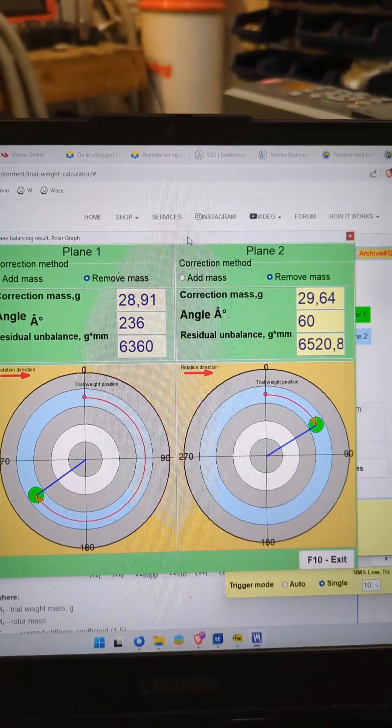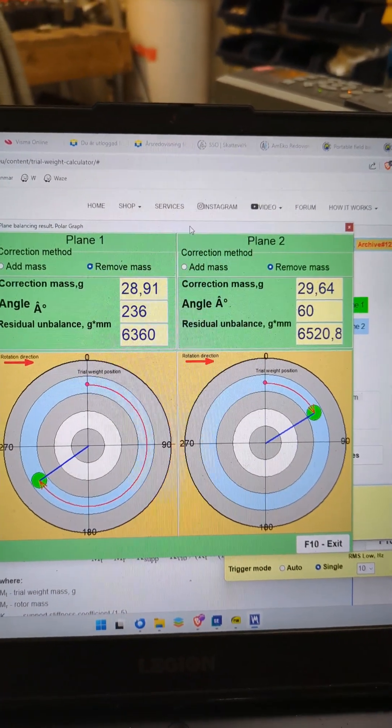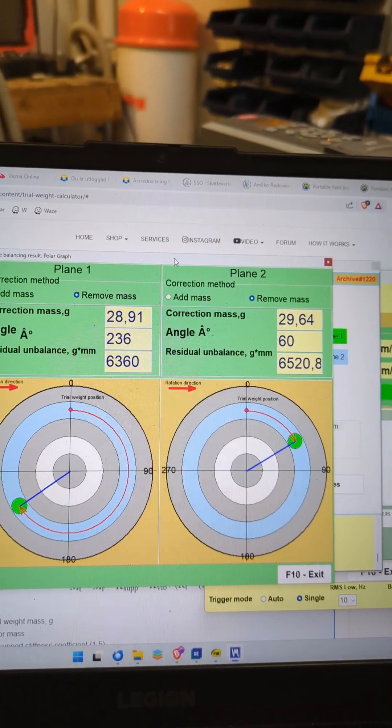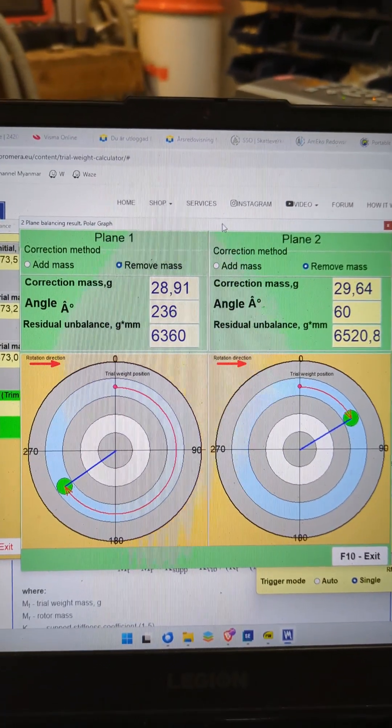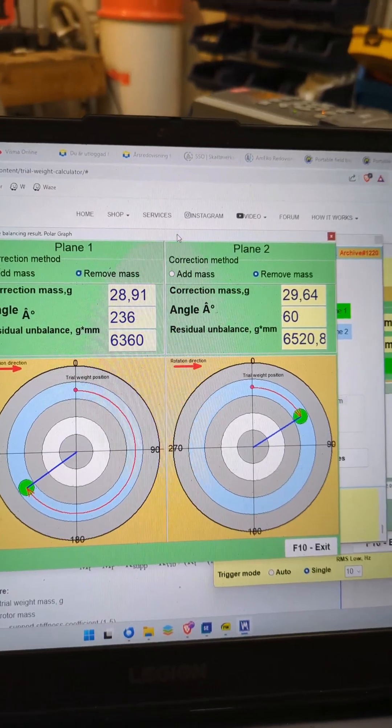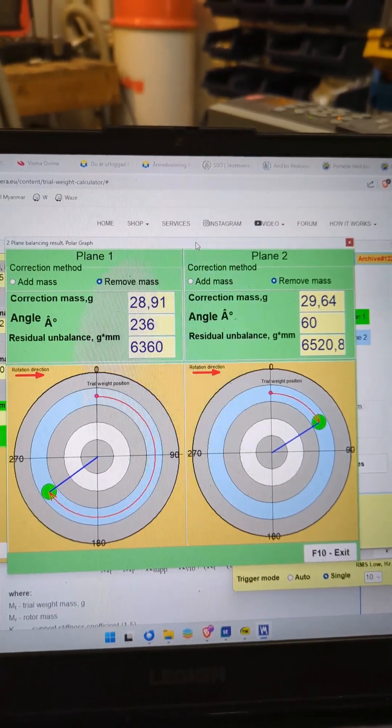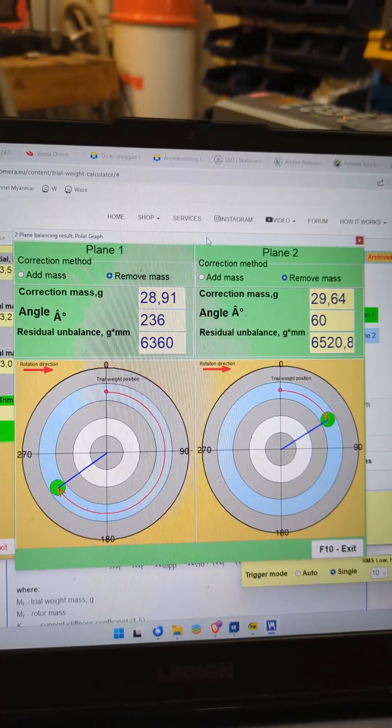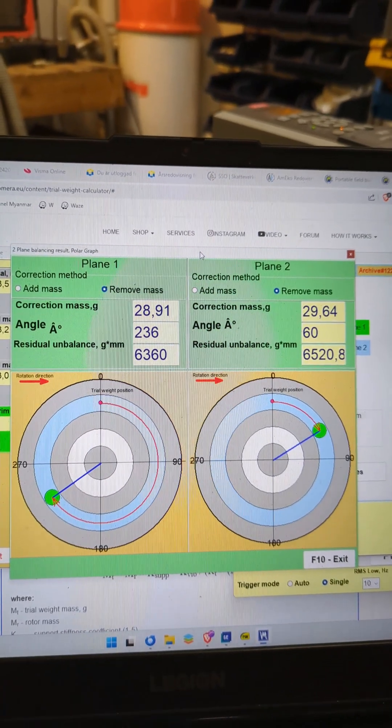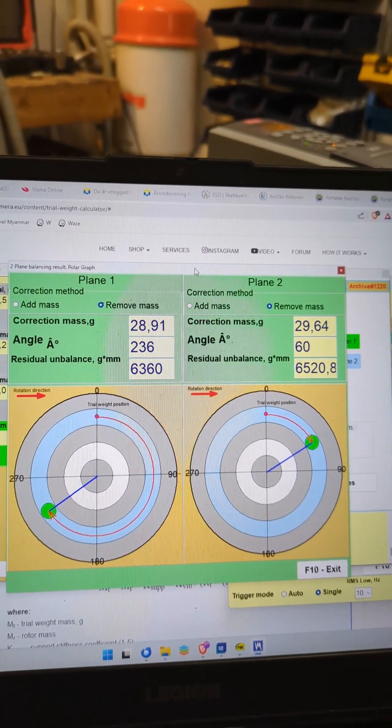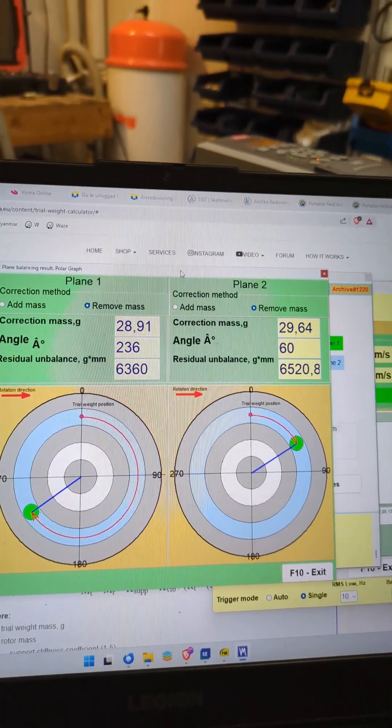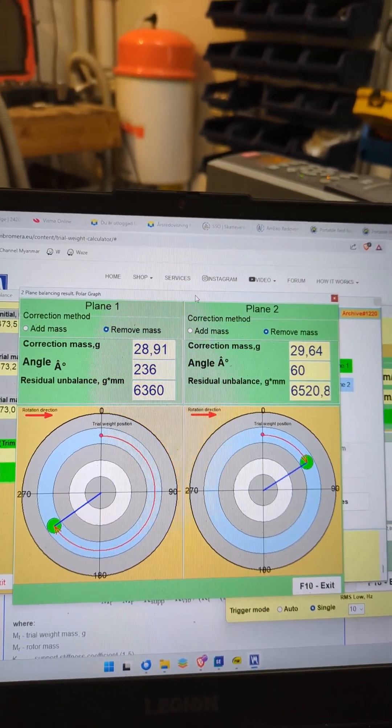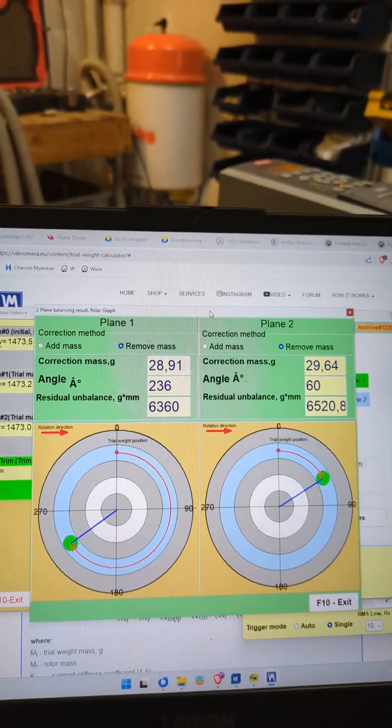So we move the trial weight from the first position to the second position in plane two. And here's a nice graph of the result and what to do. Note the very clear instruction to move in the rotating direction. You only need to know in which way the impeller or the fan wheel is rotating.